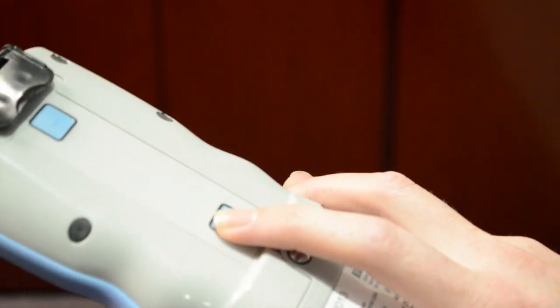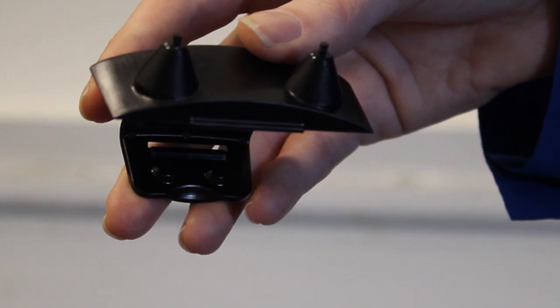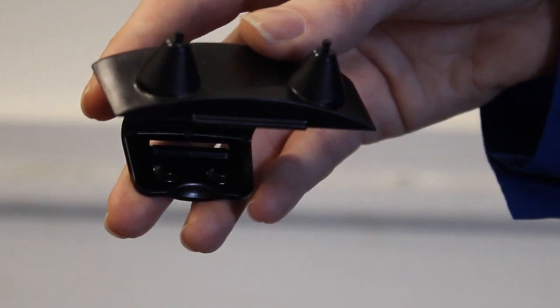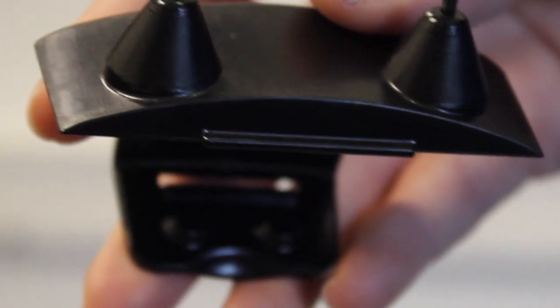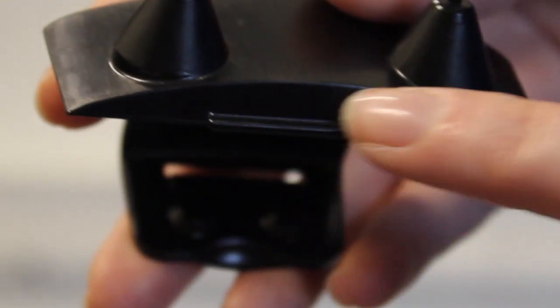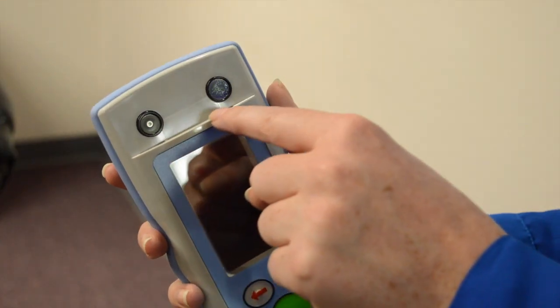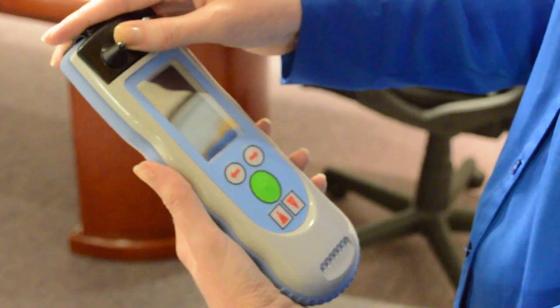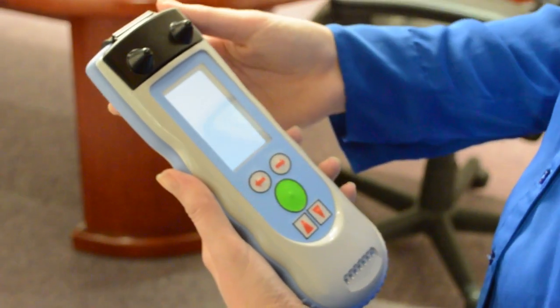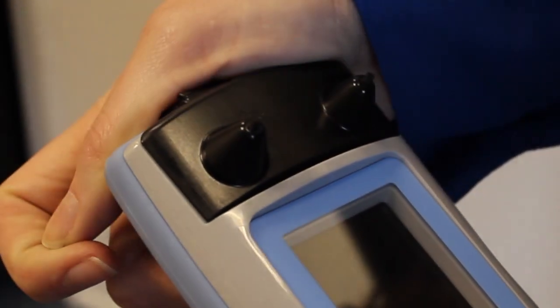To power the Infrascanner on, you must install a fiber optic disposable shield. Simply fit the straight edge groove on the shield in the cutout ledge on the front of the scanner and snap the shield in on the back side. The fiber optic shield turns the Infrascanner on, and removing the shield turns the Infrascanner off.